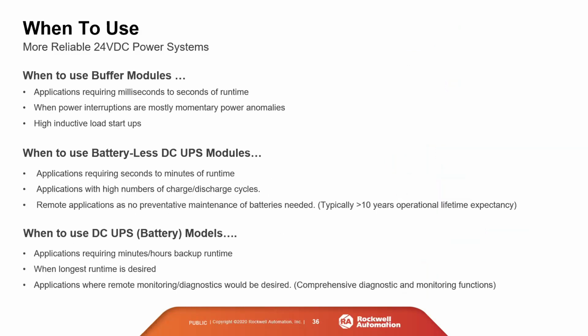So when to use buffer modules: applications requiring milliseconds to seconds of runtime, and high inductive load startups. That big motor you're starting up that causes $250,000 of downtime? You add a buffer module there and get rid of that. You can use your battery-less UPS for remote applications, as I mentioned, and applications with high numbers of charge and discharge cycles, and these provide seconds to minutes. And then your battery models are for when you need longer times, minutes to hours.